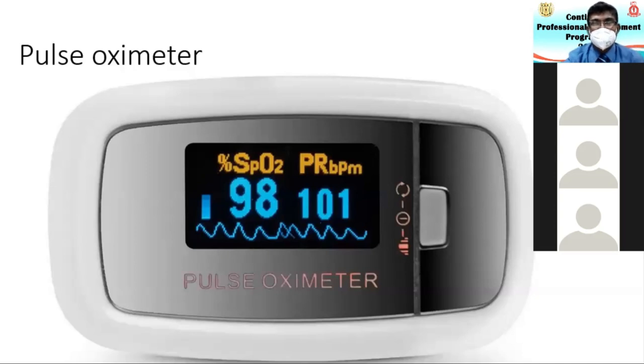Why do we say SpO2 - plethysmographic oxygen - don't get confused with saturation. It is also saturation, that's all right, but SpO2 is plethysmograph because it measures this pulsatile waveform in the finger and gives this reading. Without a pulsatile waveform, you don't get this reading. Therefore, this pulsatile waveform is very important to interpret the correct values of the pulse oximeter reading.